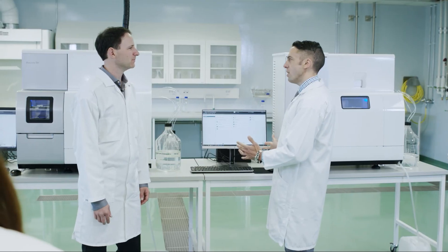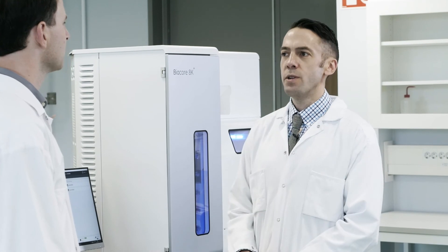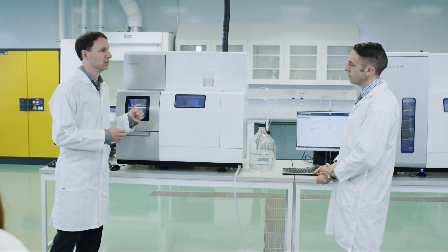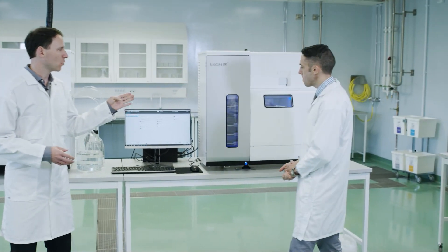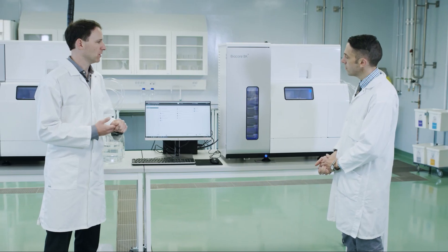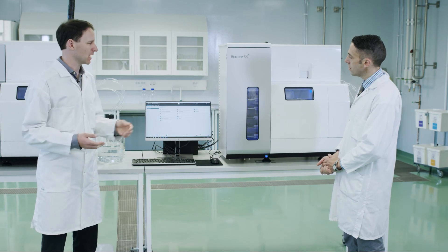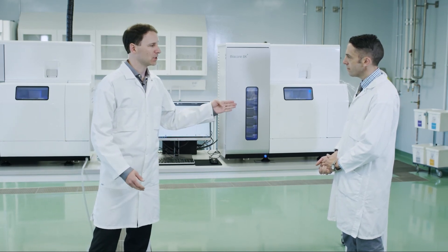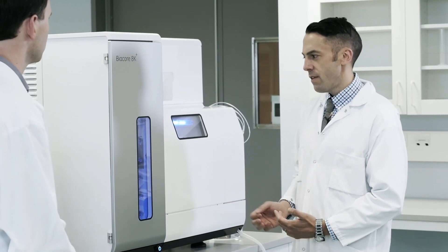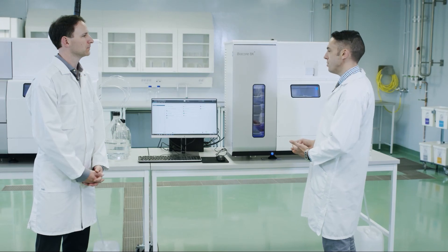There are two different types of Biacore 8K systems behind us. The Biacore 8K has places for four plates on two trays, which provides great throughput. The Biacore 8K Plus has up to 12 plates on six trays, holding over a maximum of 4,600 samples for very long unattended run time. In addition, the Biacore 8K Plus has a buffer selector valve to allow continuous evaluation using up to four different running buffers — significantly reducing dead time in the lab.